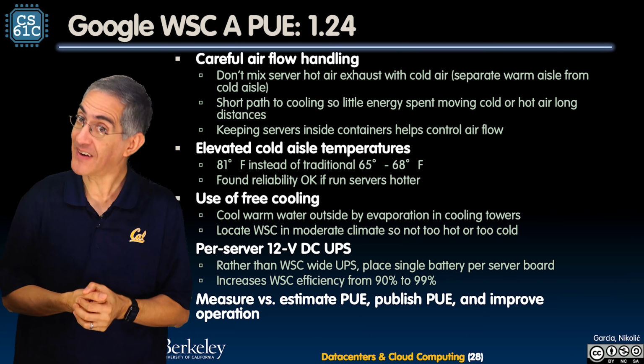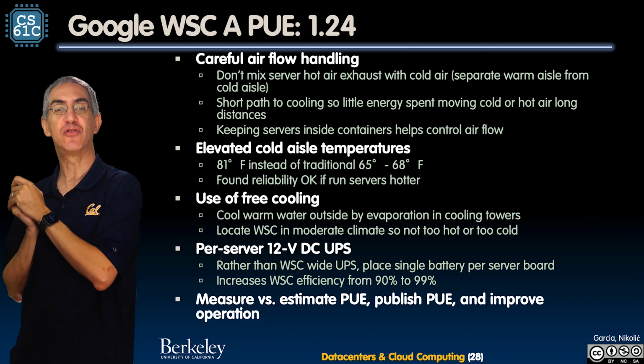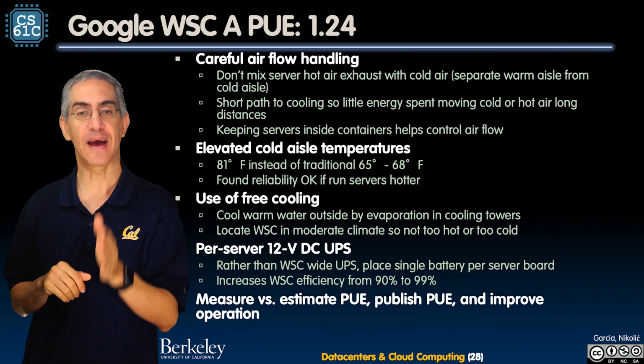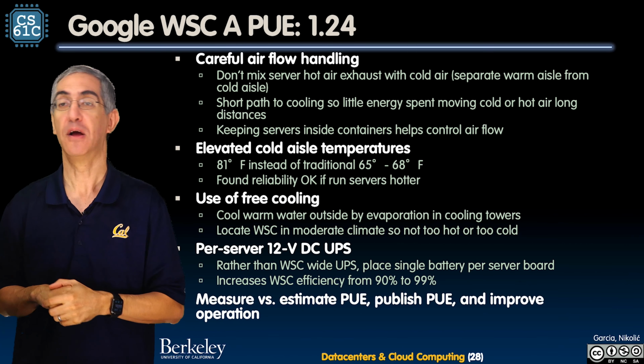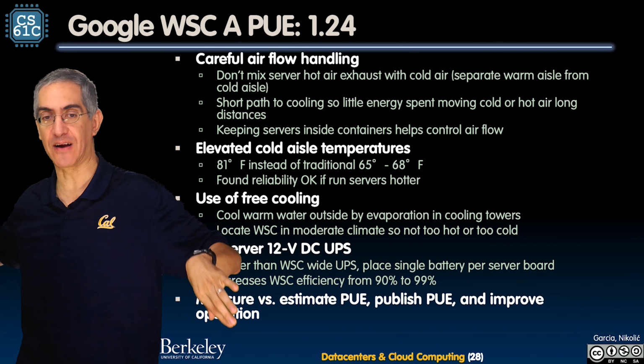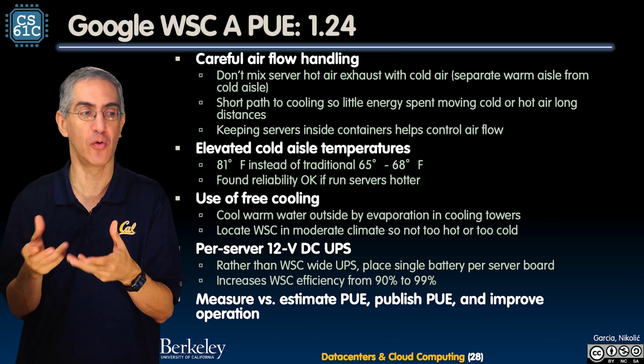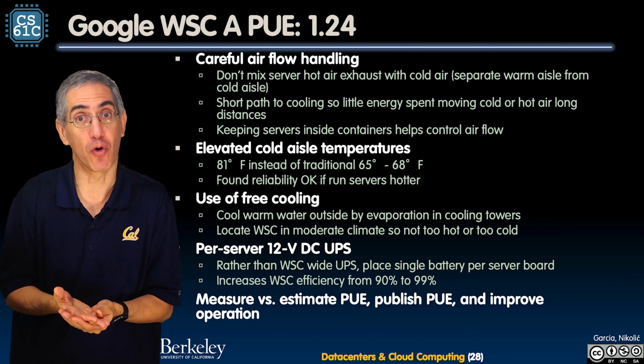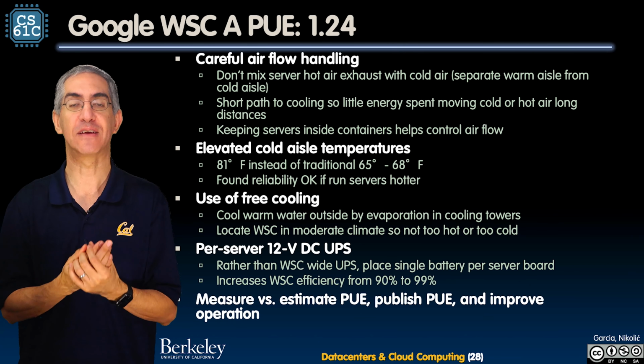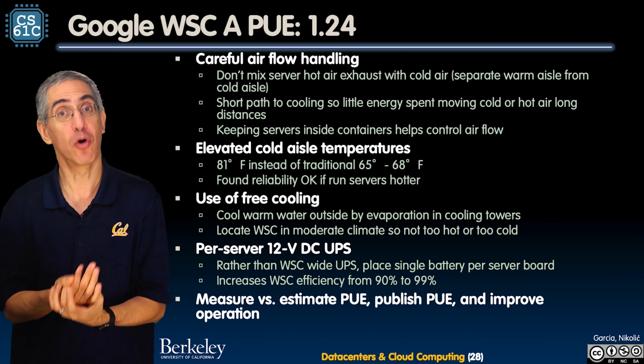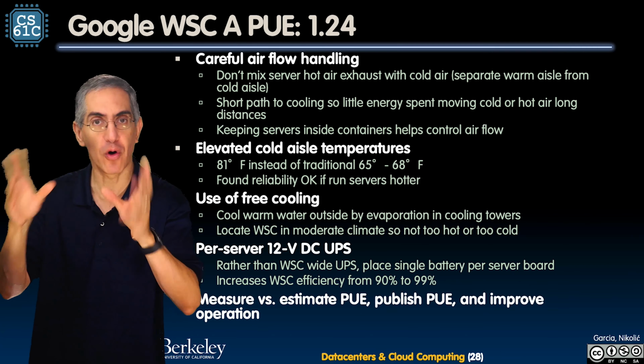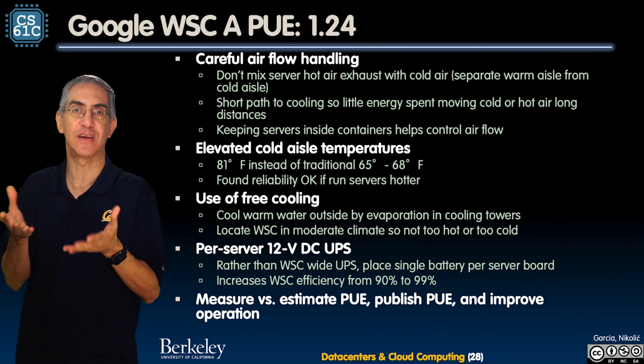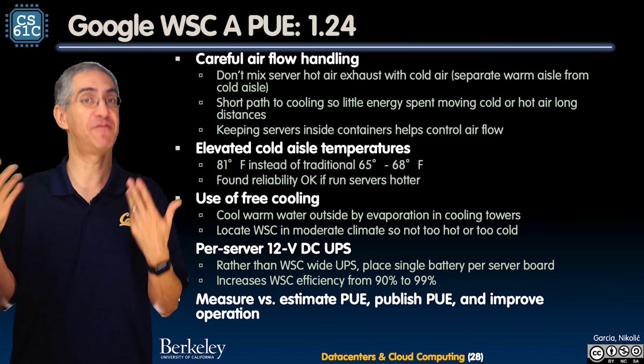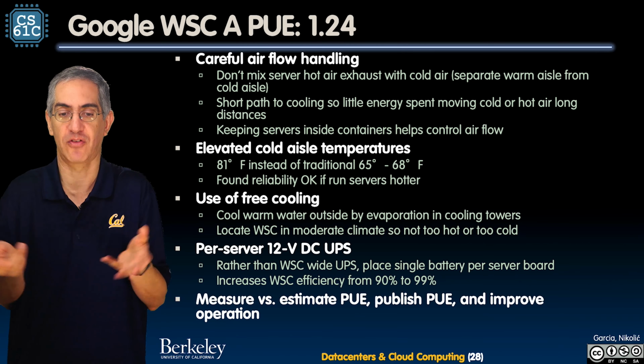They also learned, which is funny, that you can elevate the cold aisle air temperature. Normally you walk into a server room and it's pretty cold. They've learned you can actually keep server rooms warmer without machine failures. The worry is that a higher elevated temperature around the machines will cause failures, things overheating.